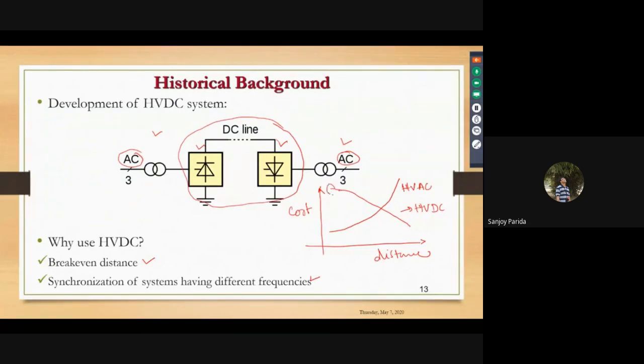That means the initial cost for the HVDC system is very high, because we are using different converters, specifically high voltage converters, which are very costly. In the HVAC system, the initial cost is very low, if we compare. But as distance increases, the HVAC system cost will increase, whereas the HVDC system cost will decrease. We see an intersection point here, and if we put a projection, this gives us the break-even distance, as it's known in technical terms.